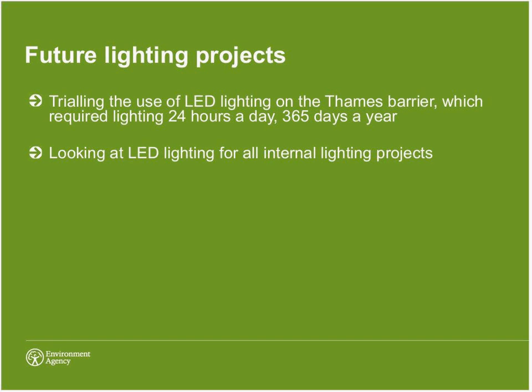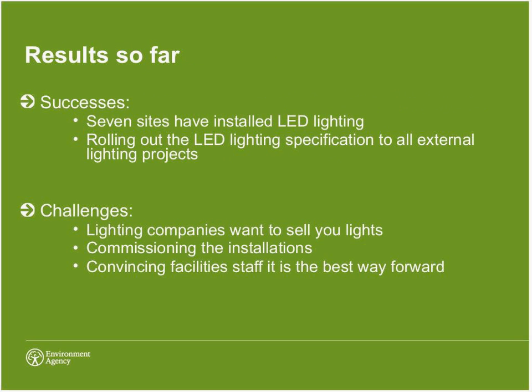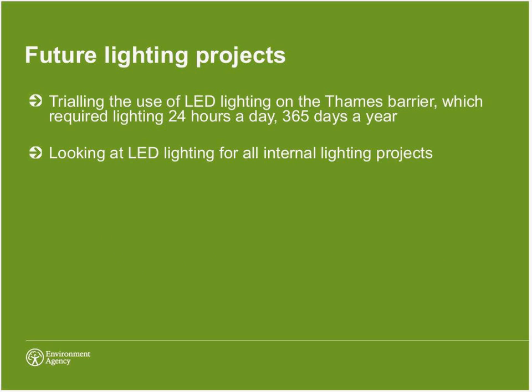The next challenge for us, I guess, is that I think we're at a tipping point with internal office lighting. About 8 months ago, we published a standard on how we would approach lighting projects, and it was very much a mixed mode approach. The cost of LEDs was still fairly high, and the energy savings were similar to T5 high frequency. We were advocating we'll still go with T5 high frequency in open plan areas, but we would introduce LED in hard to access areas, stairways, places like that, cores which get left on longer hours, which again justified the payback period for them.